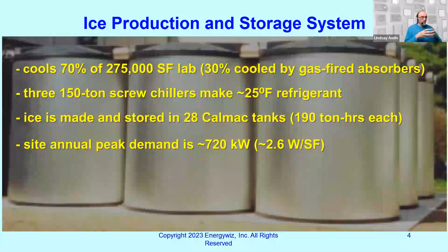The site annual peak demand, keep in mind it's a 275,000 square foot lab. The peak summer demand is only 720 kW. Peak demand is only 2.6 watts per square foot. And this is what it was even 20 years ago. So you get an idea there how much you can reduce your peak demand, even for an energy intensive place like a laboratory, by using thermal storage to get at that load, which is your chillers.